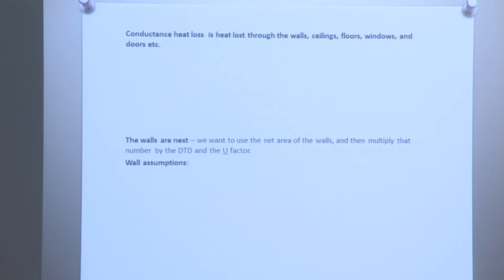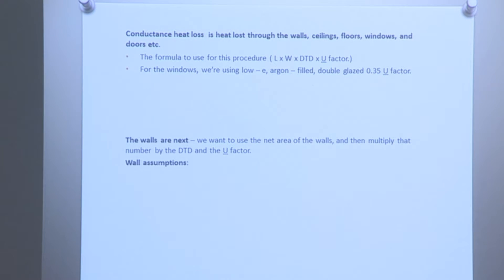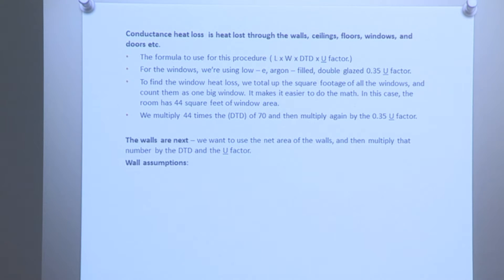Conductive heat loss is heat loss through walls, ceilings, floors, windows, doors, etc. The formula is: length times width times design temperature difference times the U-factor. For the windows, we're using low-E argon-filled double-pane glass with a U-factor of 0.35. To find the window heat loss, total up the square footage of all the windows and count them as one big window — in this case, the room has 44 square feet of window. We multiply 44 times the design temperature difference of 70 and then multiply by the U-factor 0.35: 44 times 70 times 0.35 equals 1,078 BTUs of heat loss for the windows.